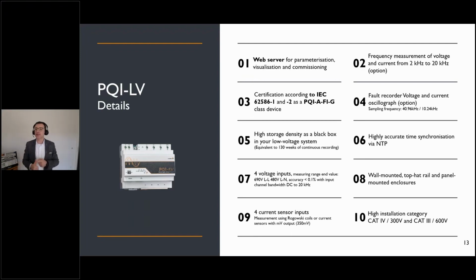The device is able to be synchronized via NTP time synchronization. It can be directly installed in CAT4 and CAT3 systems with measurement inputs L1, L2, L3, and neutral, so 4 measurement inputs. A lot of devices only have 3 measurement inputs, up to 690 volt line to line, which helps you provide the device for industry segments as well as wind farm applications.